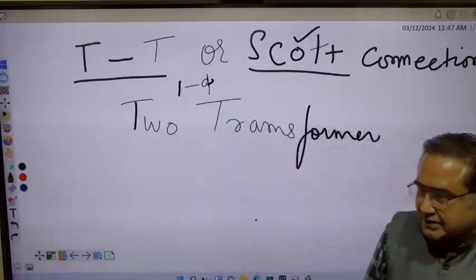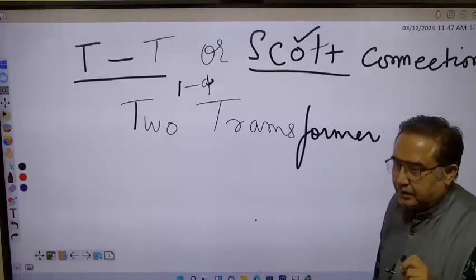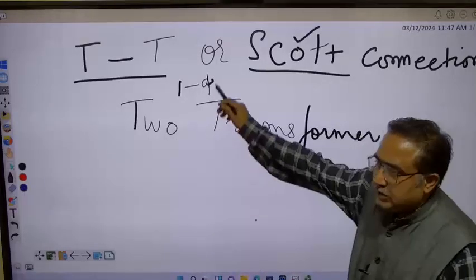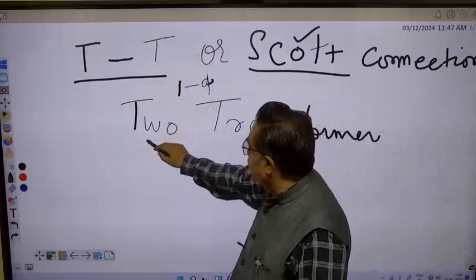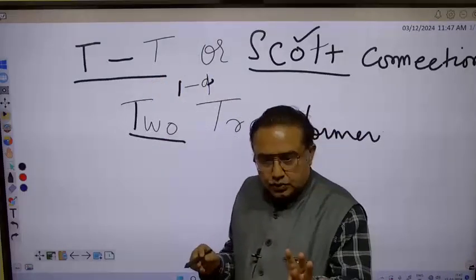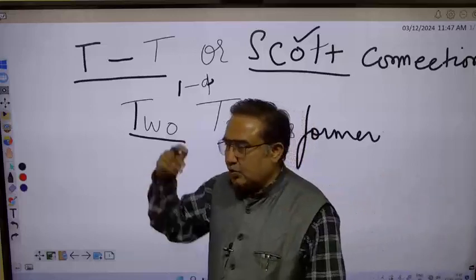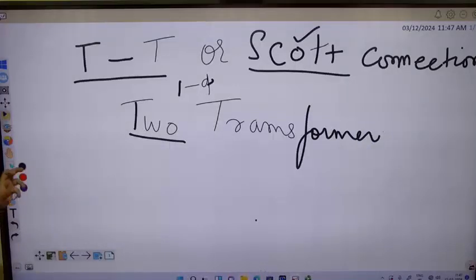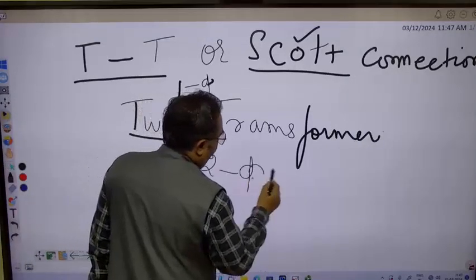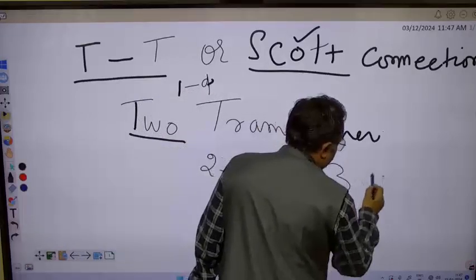But in these two special cases, VV connection or TT connection, we will be utilizing only two transformers, meaning two windings on the primary side and two windings on the secondary side. So basically this method is also known as two phase to three phase conversion method.